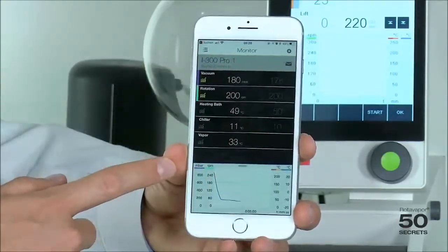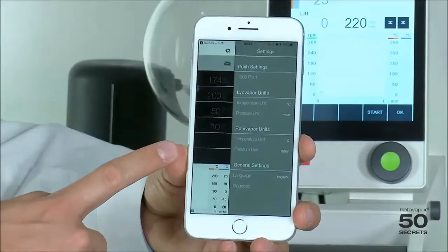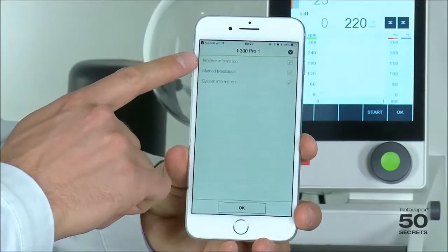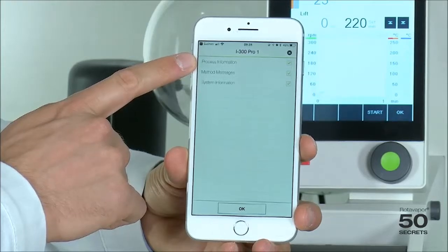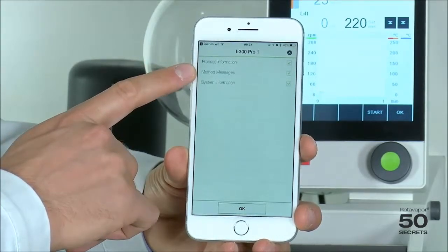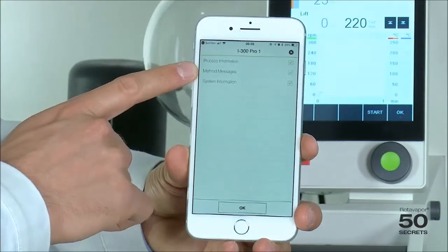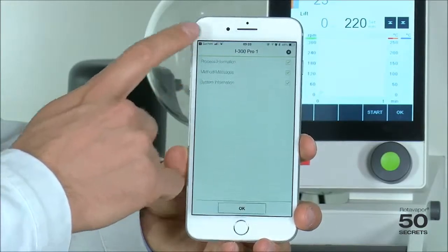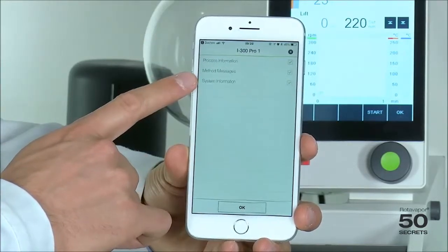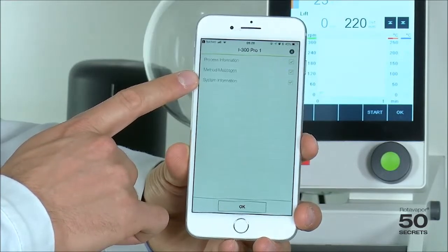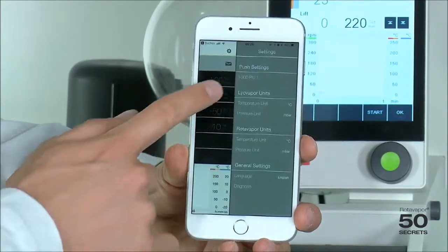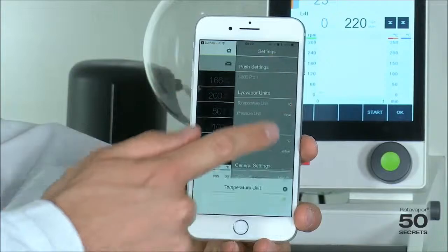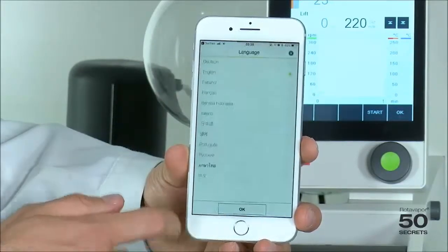You can really try it out. In addition, you can go into the settings and change the push settings. For the first option, you get process information such as if the process is finished, started, etc. Method messages — a special concept for rotavapor — appear when running methods with messages such as 'remove receiving flask.' There is also system information such as errors. You can change the units, for example to degrees Celsius or Fahrenheit, and general settings such as the language.